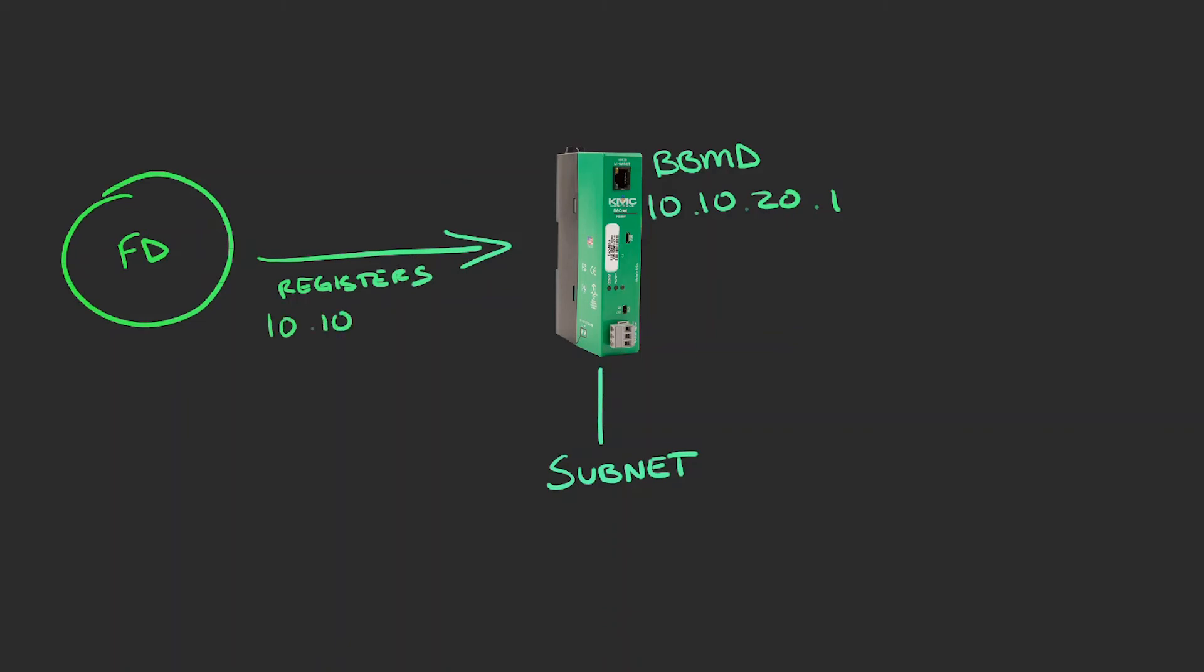The downside of the foreign device is it has a limited time to be registered. This is called the time to live. The default time is usually 30 minutes, which means every 30 minutes the foreign device must re-register with the BBMD.